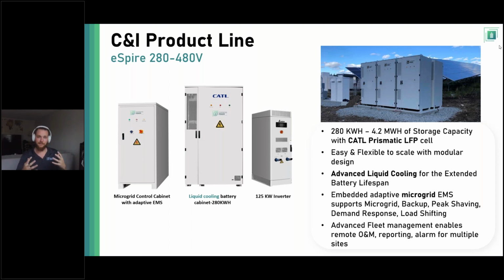In terms of scalability, you can see the first bullet point: 280 kilowatt hours up to 4.2 megawatt hours. The way that works is we can put 5 of those 125 kW inverters together to get 625 kW of 480 volt power, and we could put 3 battery cabinets to each one of those 5 inverters. That's a total of 15 battery cabinets in a max configuration, so 15 times 280 kilowatt hours, roughly 4.2 megawatt hours of energy storage.